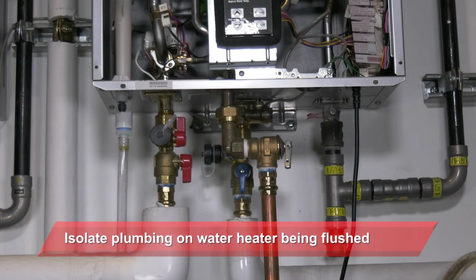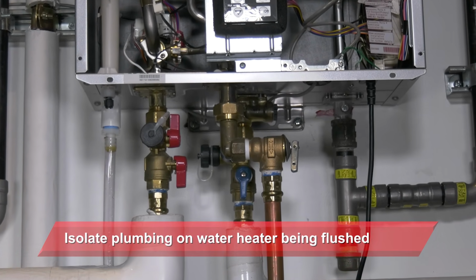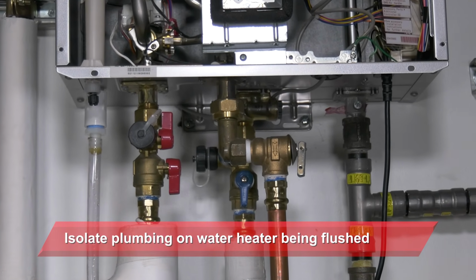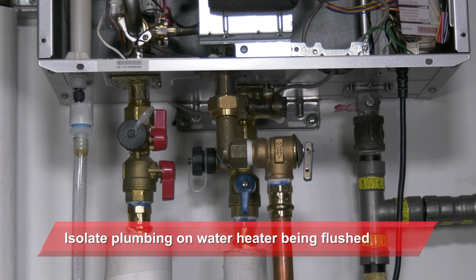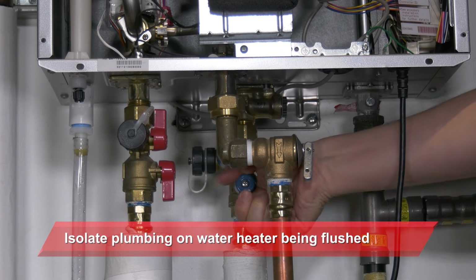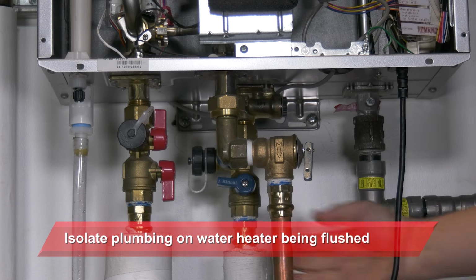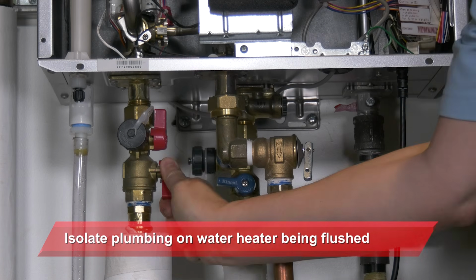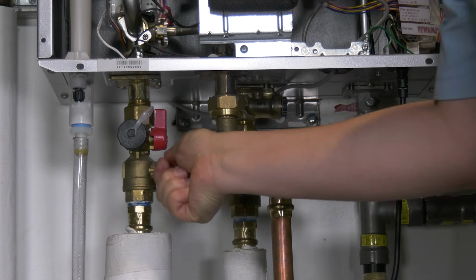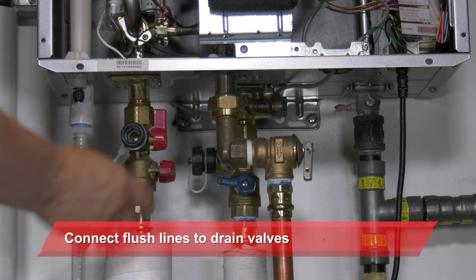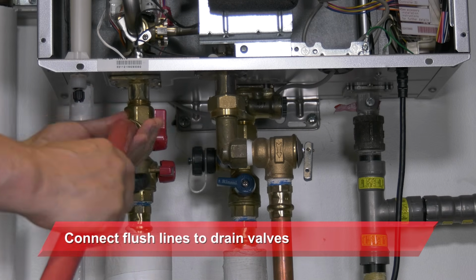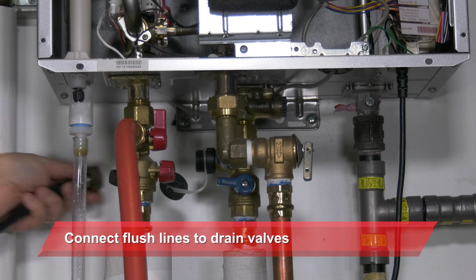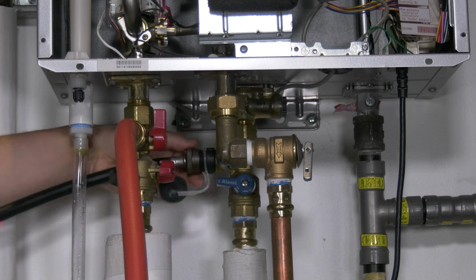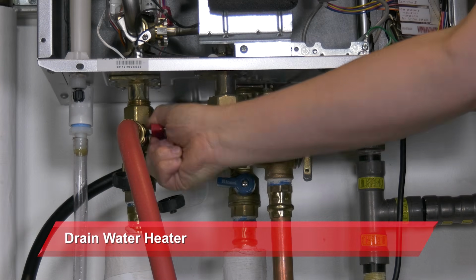Now, a flush procedure is one of the many reasons all tankless water heaters need these valves installed. In fact, they're included with many Rinnai tankless water heaters. So we're going to turn off the cold inlet valve coming from the supply and the hot outlet valve going to the plumbing system. We're also going to connect a drain line to the hot drain down valve and the cold drain down valve. Now we're going to open these valves and drain the water heater completely.